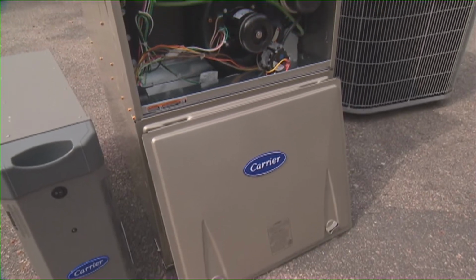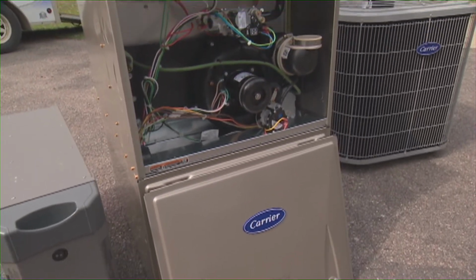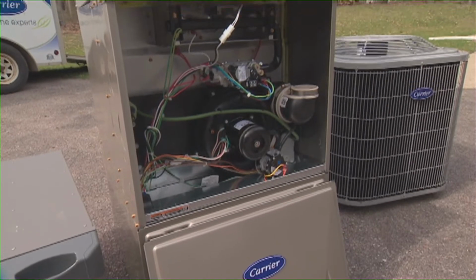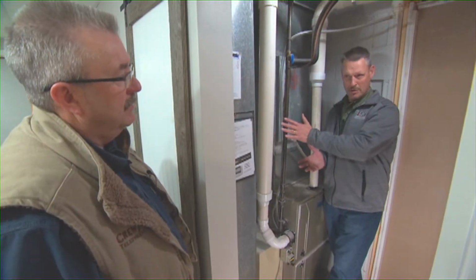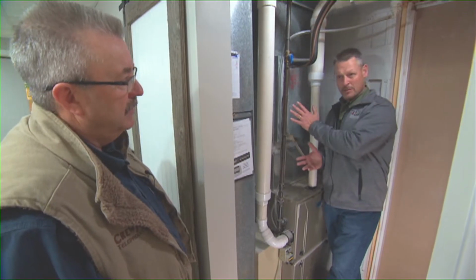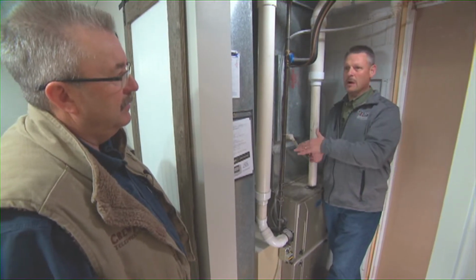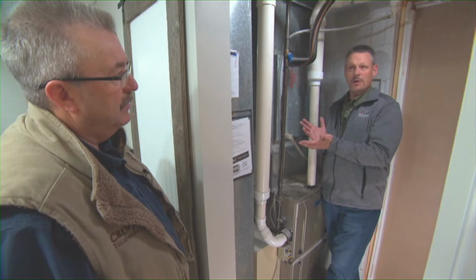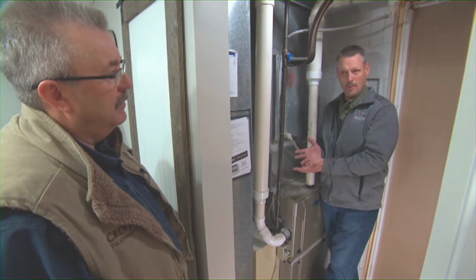So what we're doing is downsizing the furnace to the next smaller BTU capacity, and we're putting in two-stage. So it'll better match the full heat load of the house from spring all the way to fall into winter. As it gets colder out, it will be able to run on high fire when it needs to, and run low fire when it's more mild out.